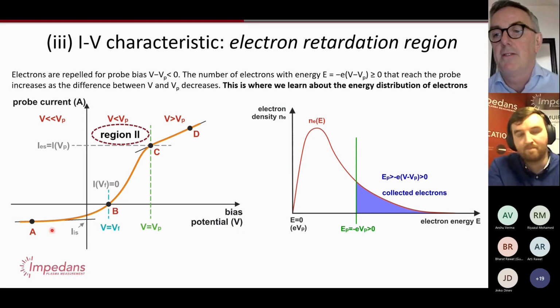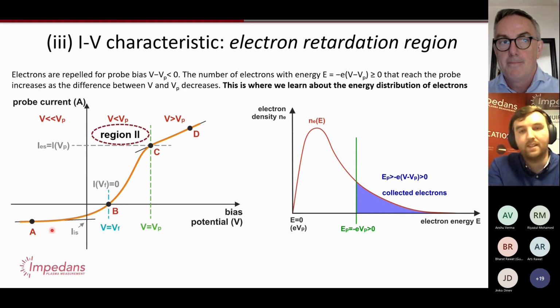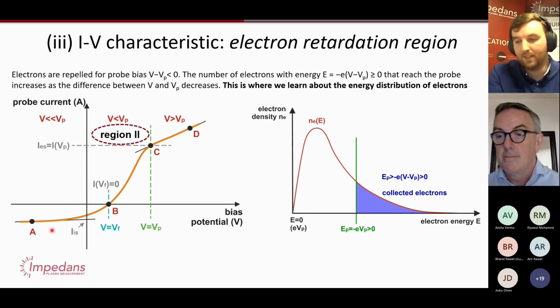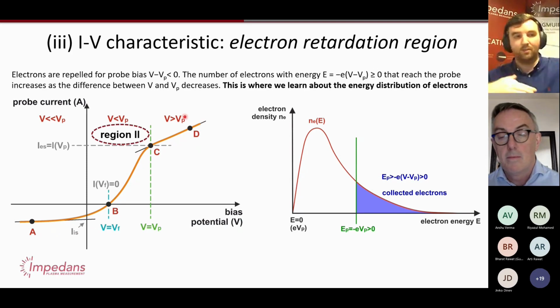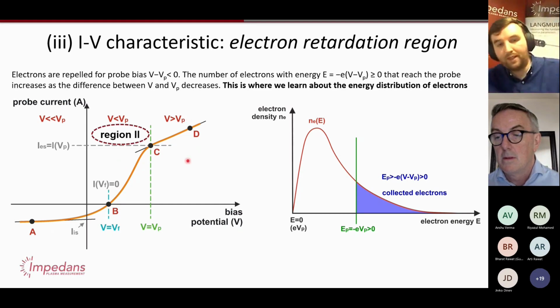Okay, so how do you know if the Langmuir probe is being impacted by the RF-driven plasmas? Yes, so I mentioned this earlier on, but basically the telltale sign is that your electron temperature is unphysical. In a CCP system, very often it's 2 to 3 eV. If you're seeing a measurement like 8 eV or something like that, it's too high. It's kind of hard to show, I don't have a diagram of it, but if you imagine that you have this IV curve here, that's an IV curve for a plasma when the voltage from the RF cycle is, say, high, and then when it's low, the whole thing is shifted to the side.